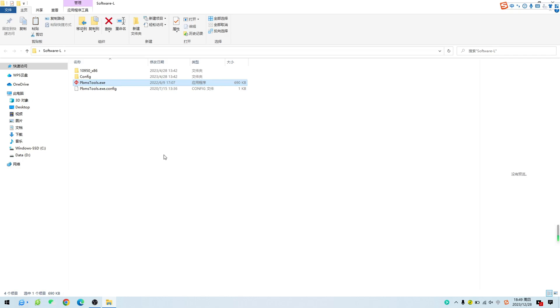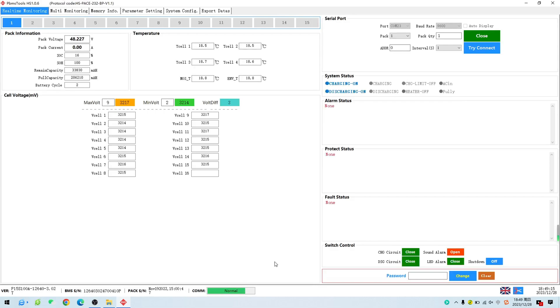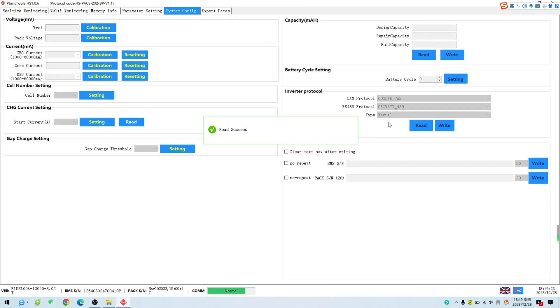Click on system setting, then click read in inverter protocol setting. Choose Voltronic for RS485 protocol, then click write. After writing, click read to check if the writing was successful. We can see the RS485 protocol is now selected as Voltronic, indicating the selection is complete.